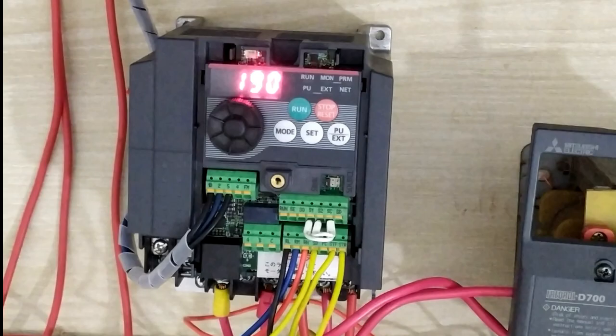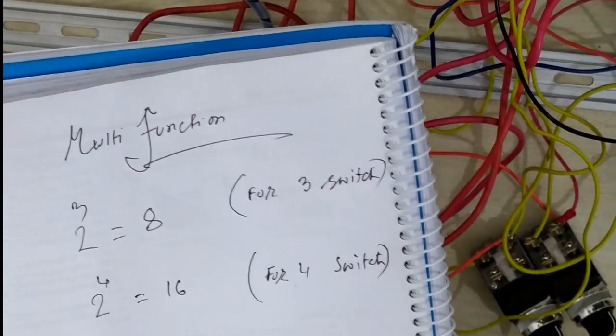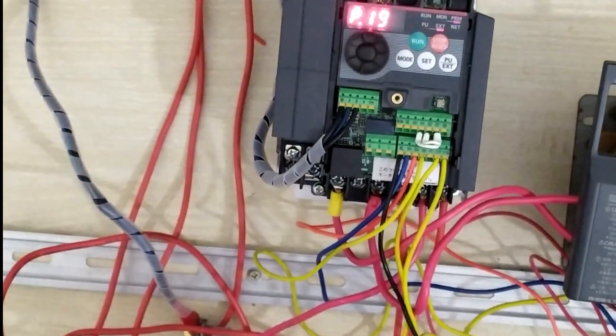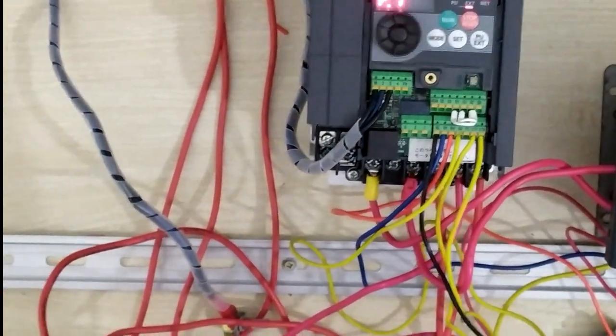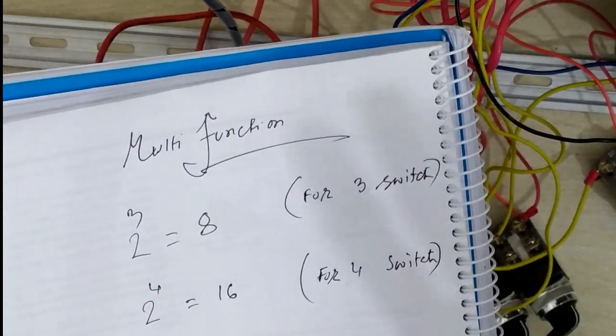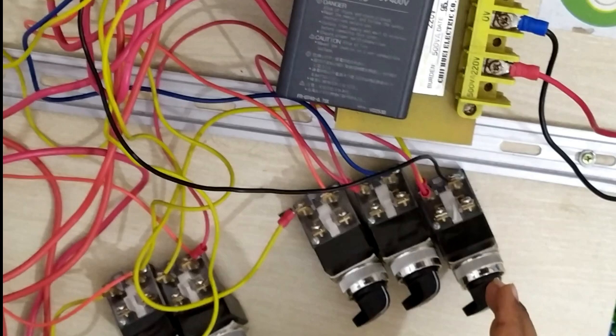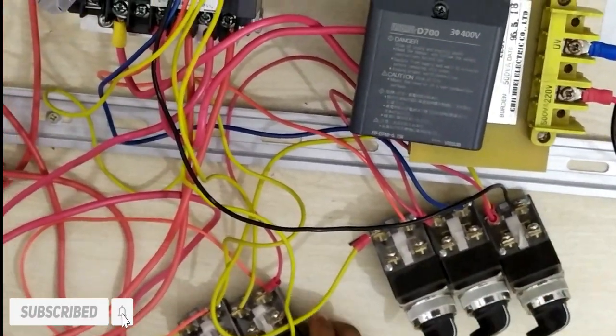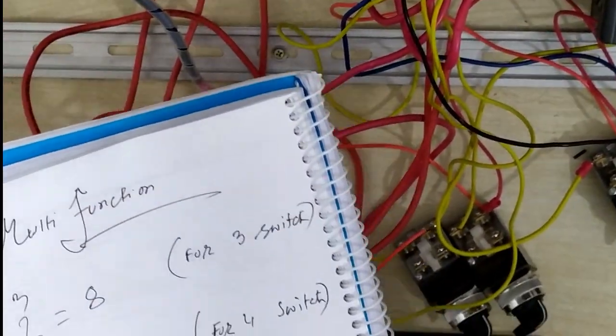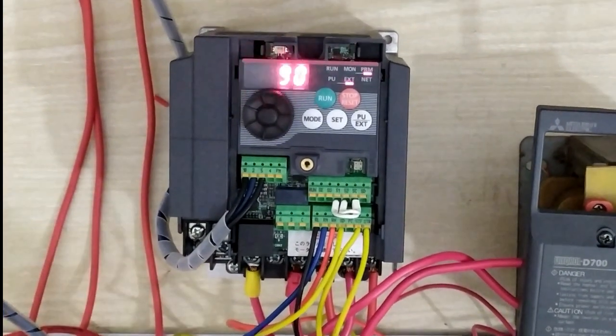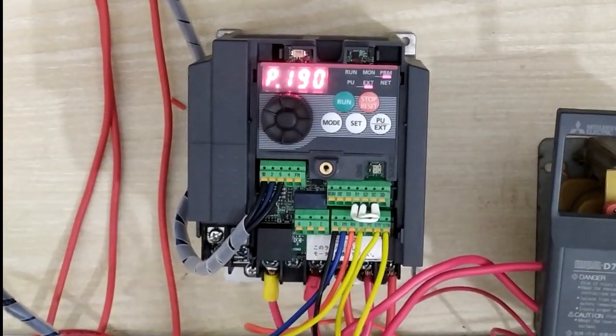I want to describe what is the multi-speed function and how to set your switches by multi-functions. We have 3 switches: RM, RL, and RH — that means 3 switches are selected and set here. The 4th is for reverse direction. We are controlling up to 50 Hz using 8 types of frequency, variously, specifically, or individually.